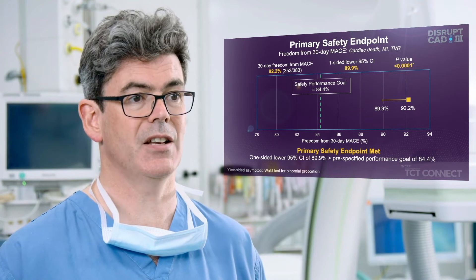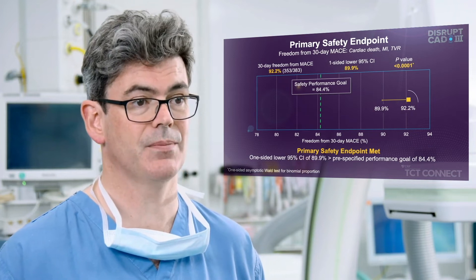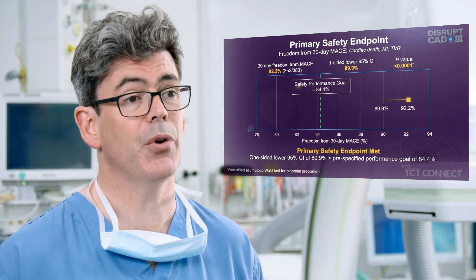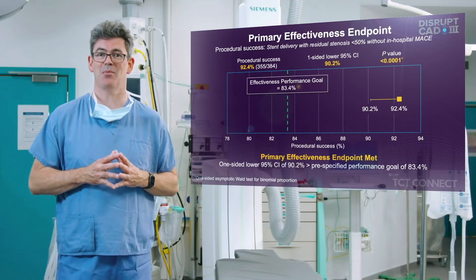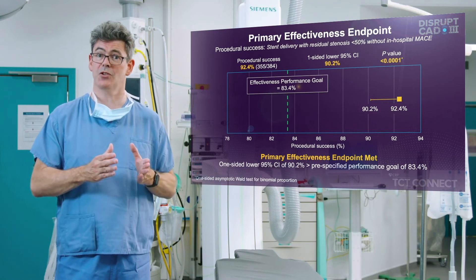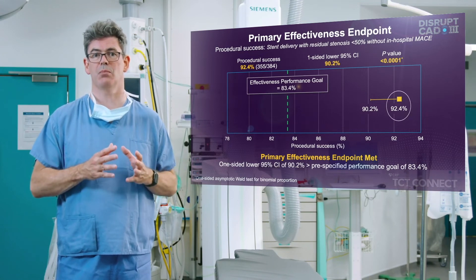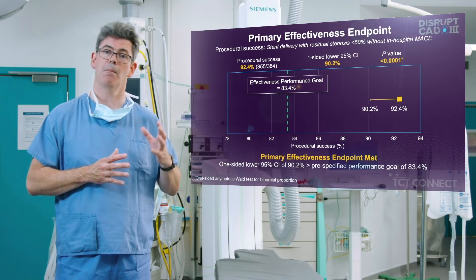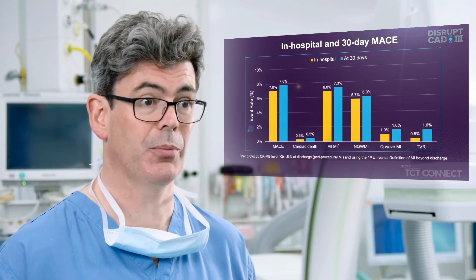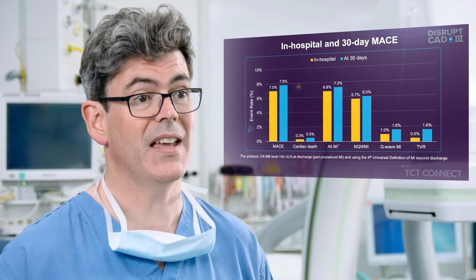The primary safety endpoint, freedom from 30-day MACE, was observed in 92.2%, with the lower confidence boundary of 89.9% meeting the safety performance goal. The primary effectiveness endpoint — stent delivery with residual stenosis less than 50% and no in-hospital MACE — was observed in 92.4%, with the lower confidence boundary of 90.2% meeting the effectiveness performance goal. In-hospital and 30-day MACE were 7% and 7.8% respectively.